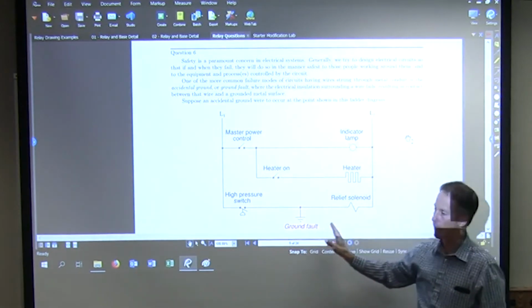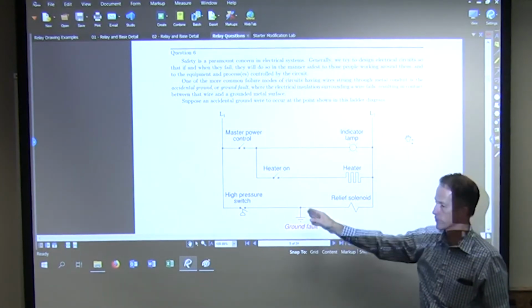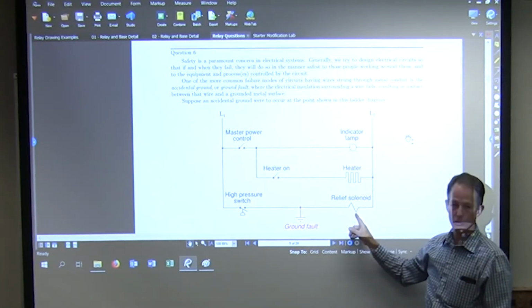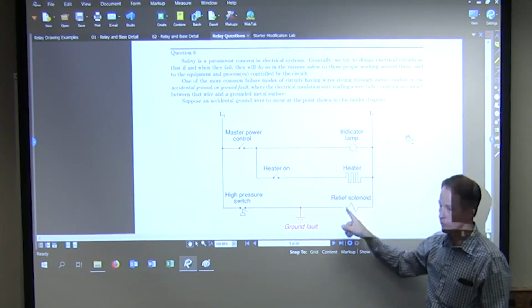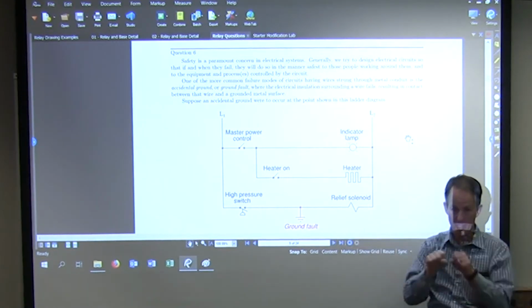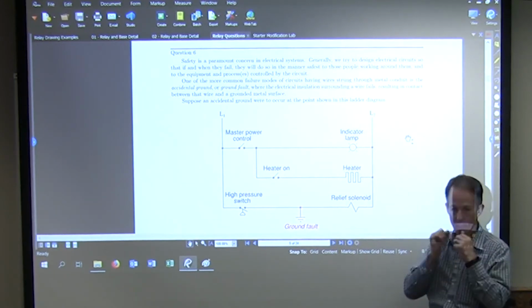I put in this ground fault. Now I have 110 volts going to ground through a 240 volt load. What's my current? Half of that. Half an amp, because this load basically resists full flow.